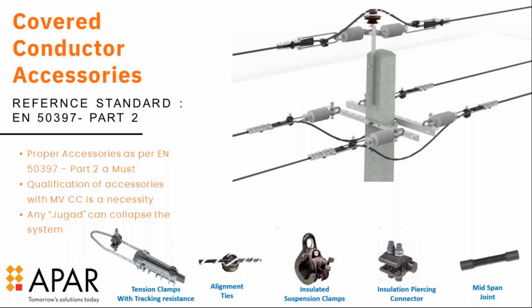If you want to reconductor an existing bare conductor network with covered conductor, you don't need to replace the poles, insulators, or cross arms. On the same insulator, cross arm, and poles, you can just take out the bare conductor and put in the covered conductor — it's so easy to install.